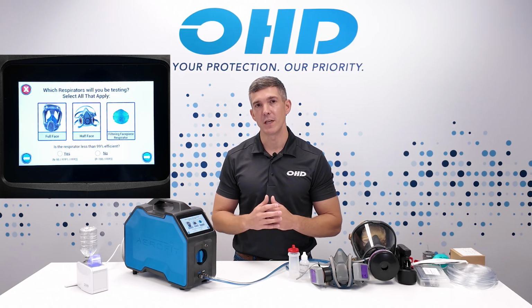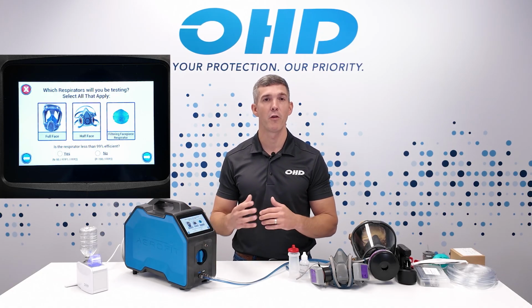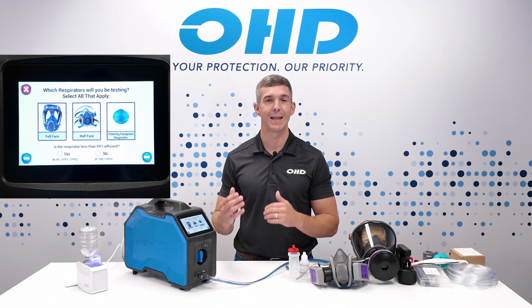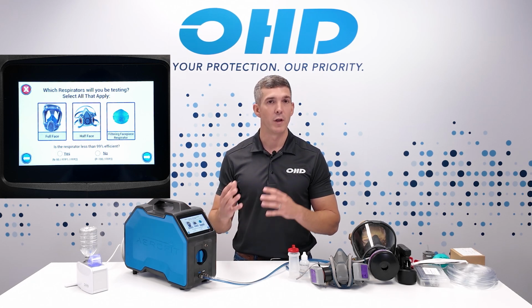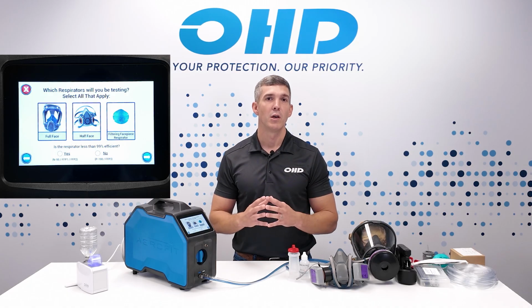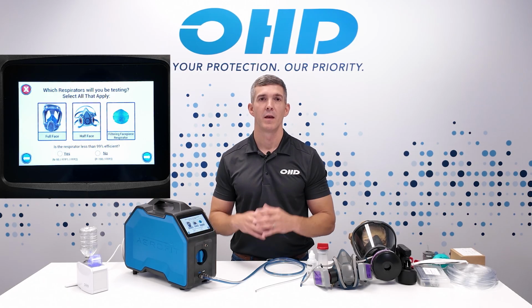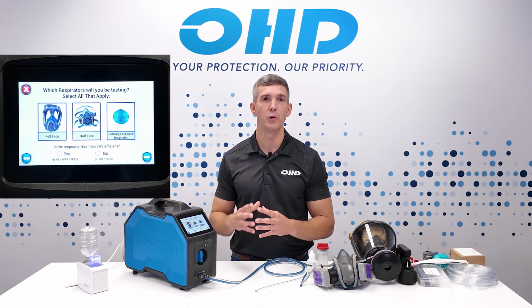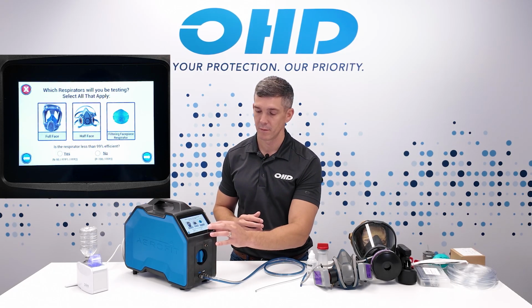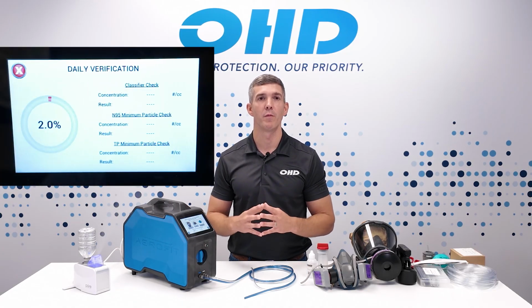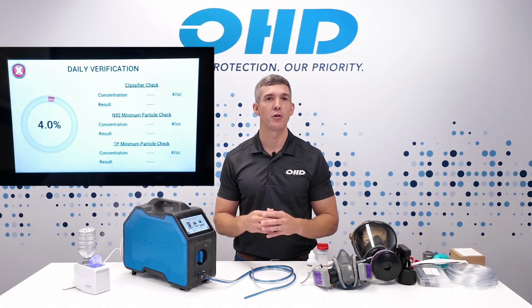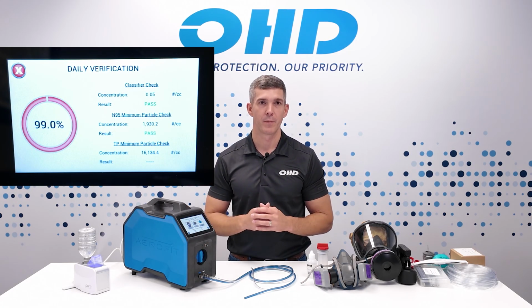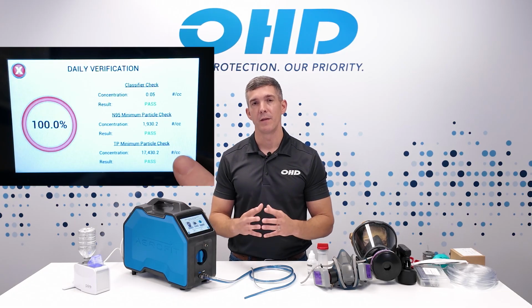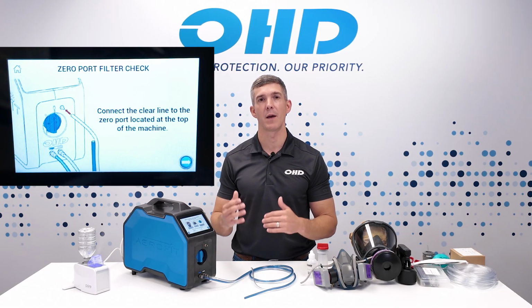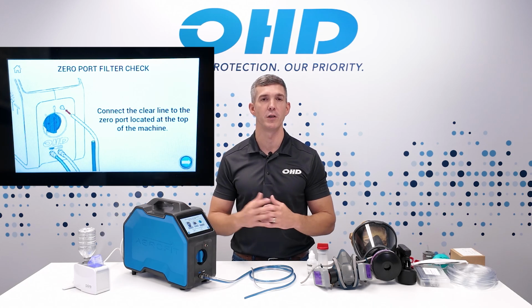If you select filtering facepiece respirators, you will be asked whether the respirator has a filter efficiency less than 99%. For N95s or FFP2s, you would select yes. After making your selections, press the blue arrow in the bottom right to advance. The AeroFit will now perform the appropriate initial checks. Make sure no tubes are connected to the zero port and that it is open to the ambient air. Once the initial checks are complete, the AeroFit will direct you to connect the clear sample line to the zero port on the front of the unit.